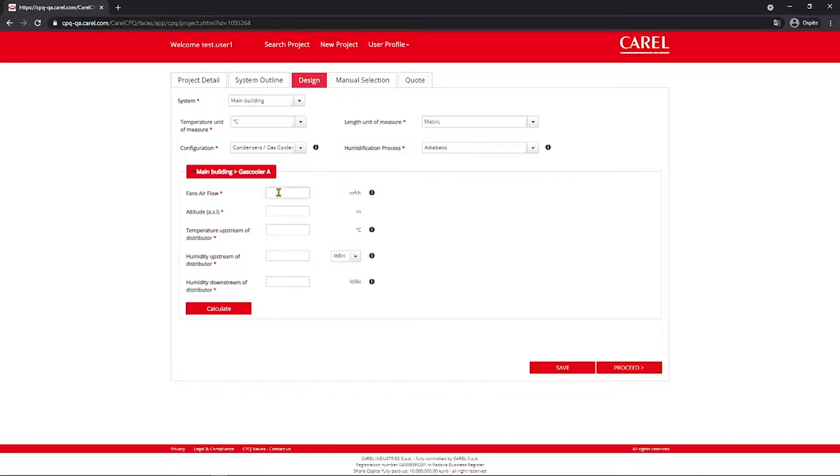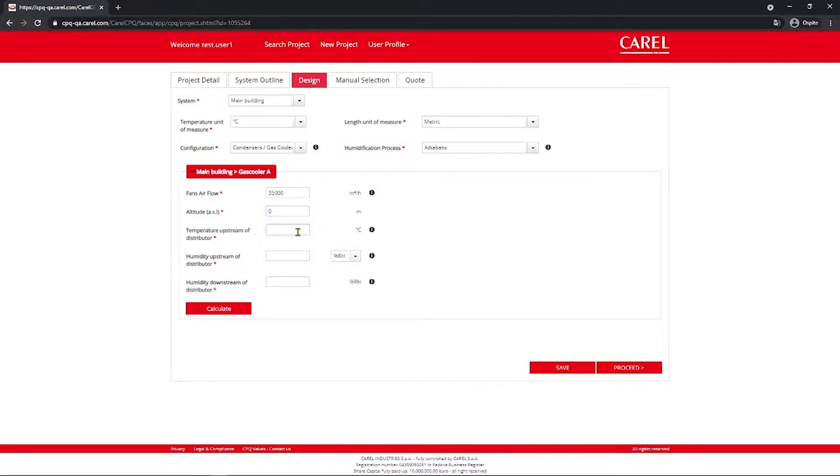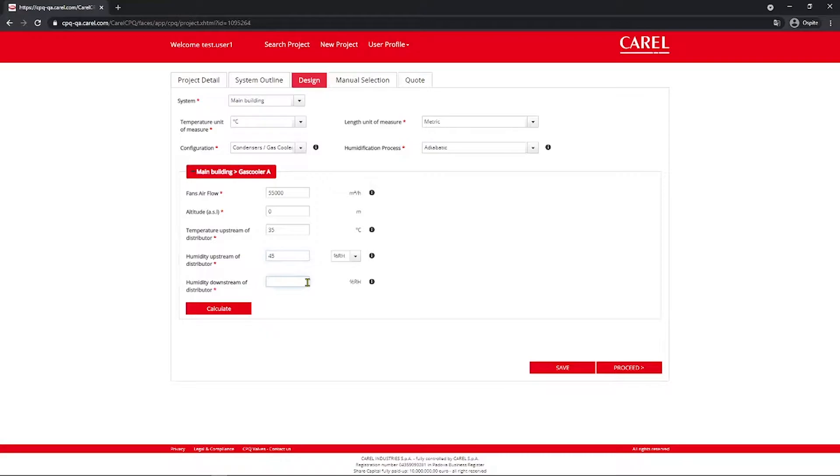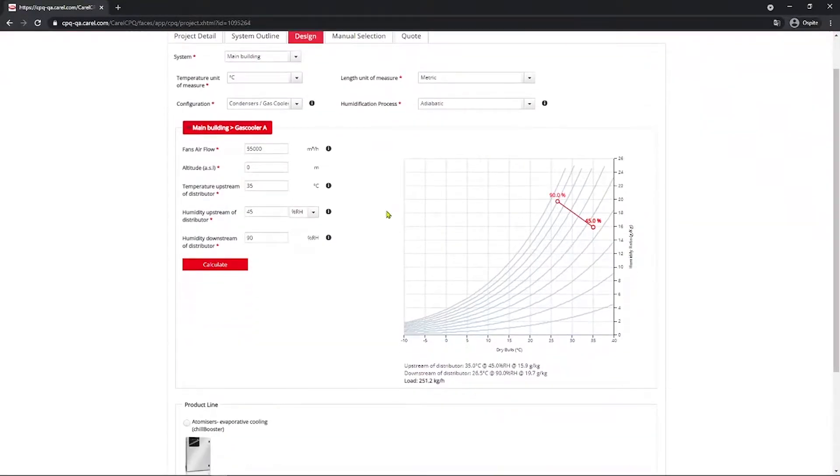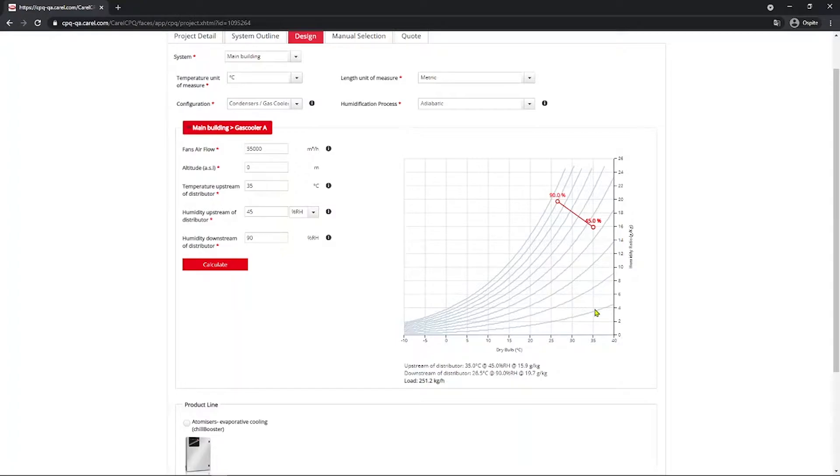Now you enter the data based on the project. For example, here you can have like 55,000. Altitude zero, so sea level. Temperature upstream of distributor, let's say 35 degrees Celsius. Humidity upstream of distributor, let's say 45%, and humidity downstream of distributor, let's say 90%. So you calculate and you can see here the thermodynamic process and the evaluated humidification load. In this case is 251.2 kg per hour.